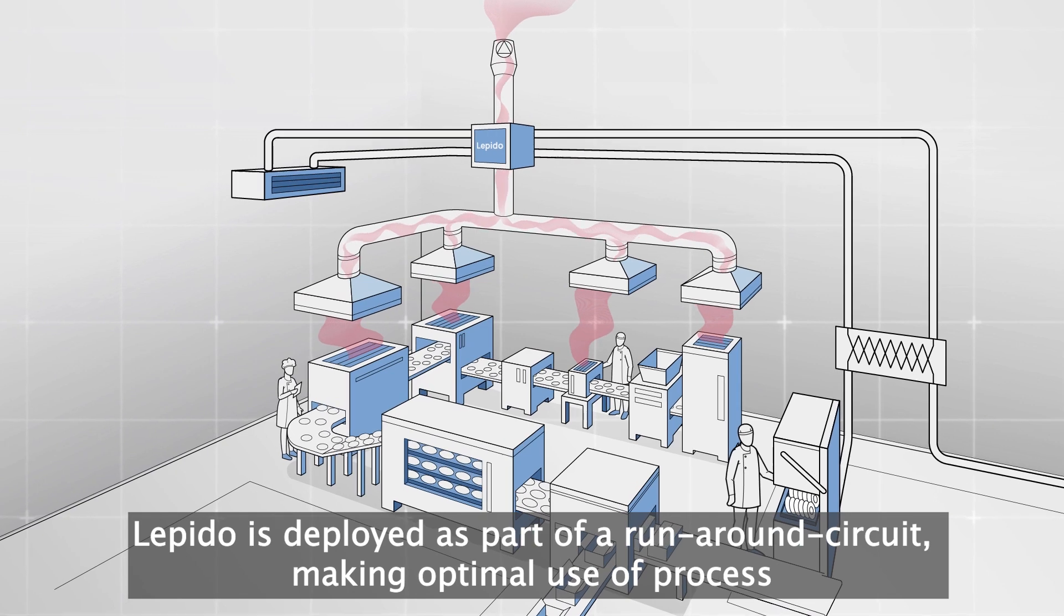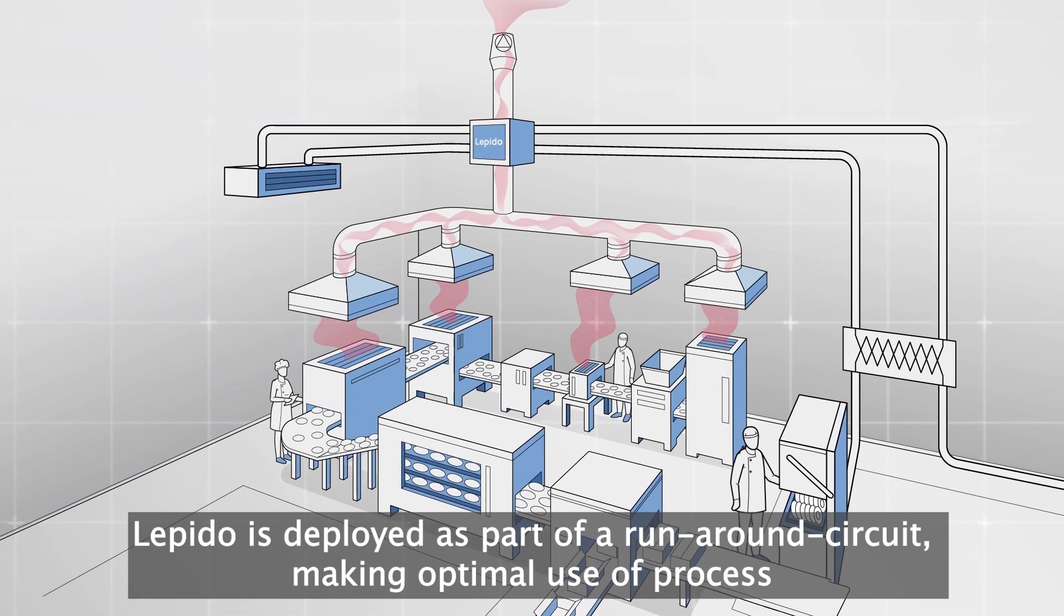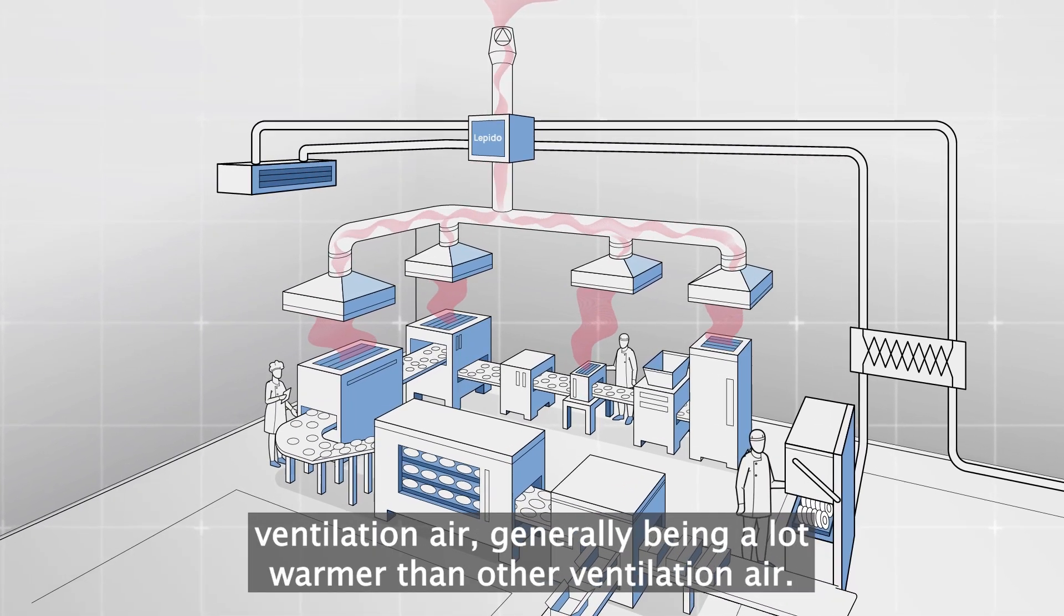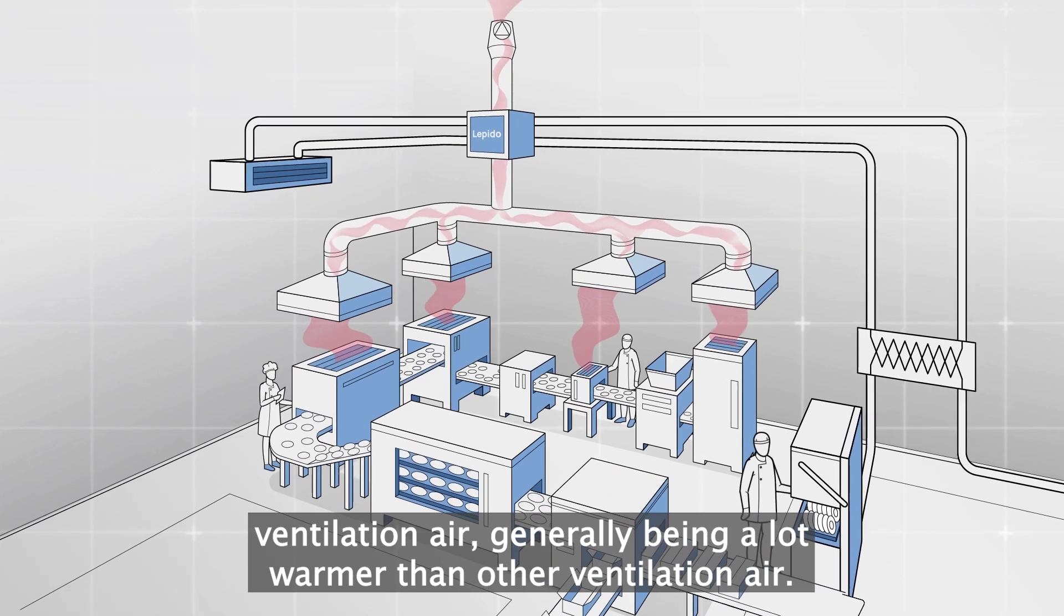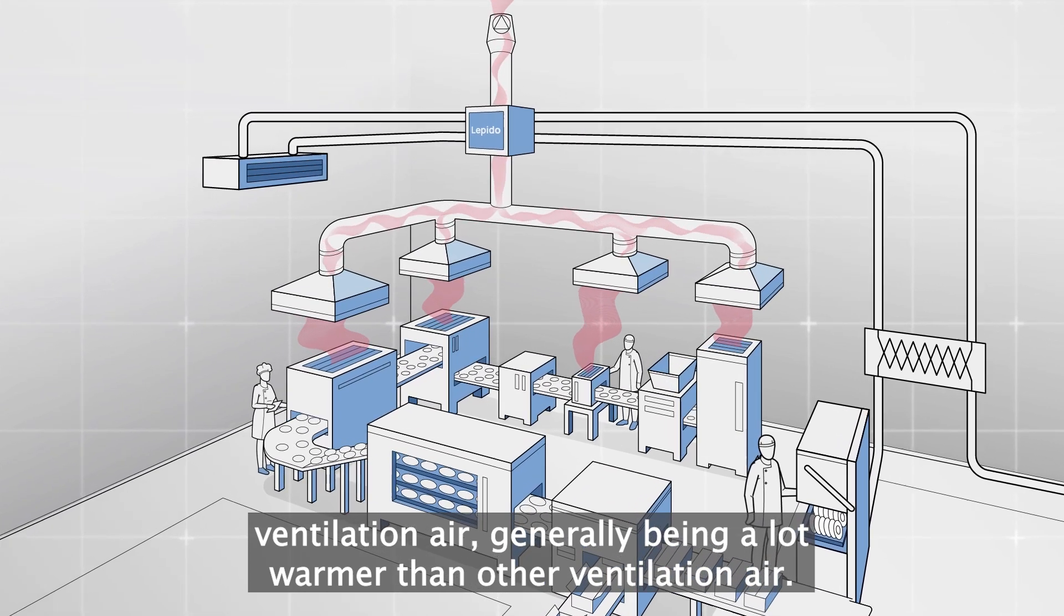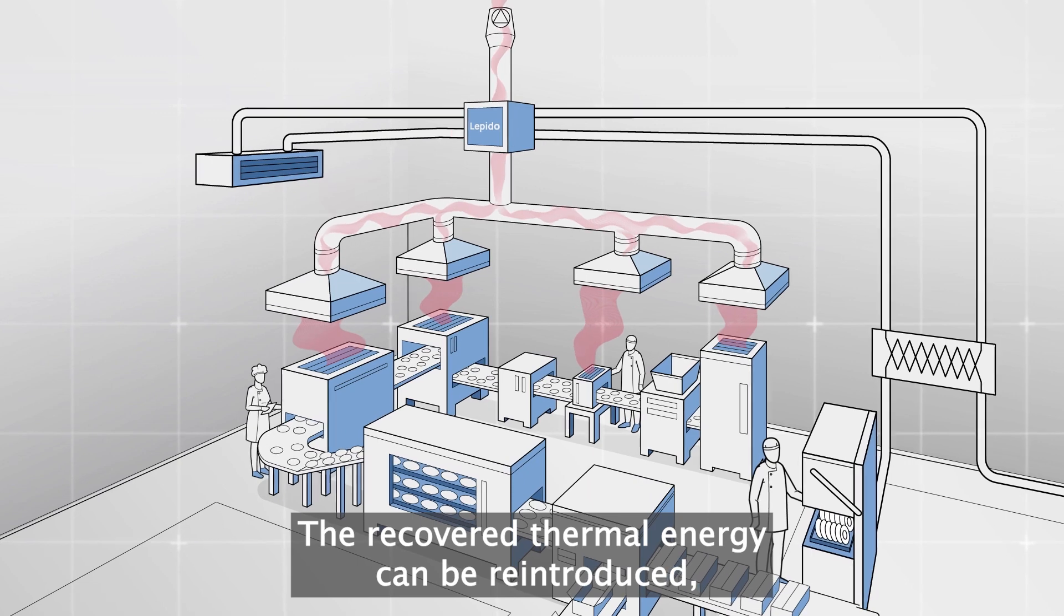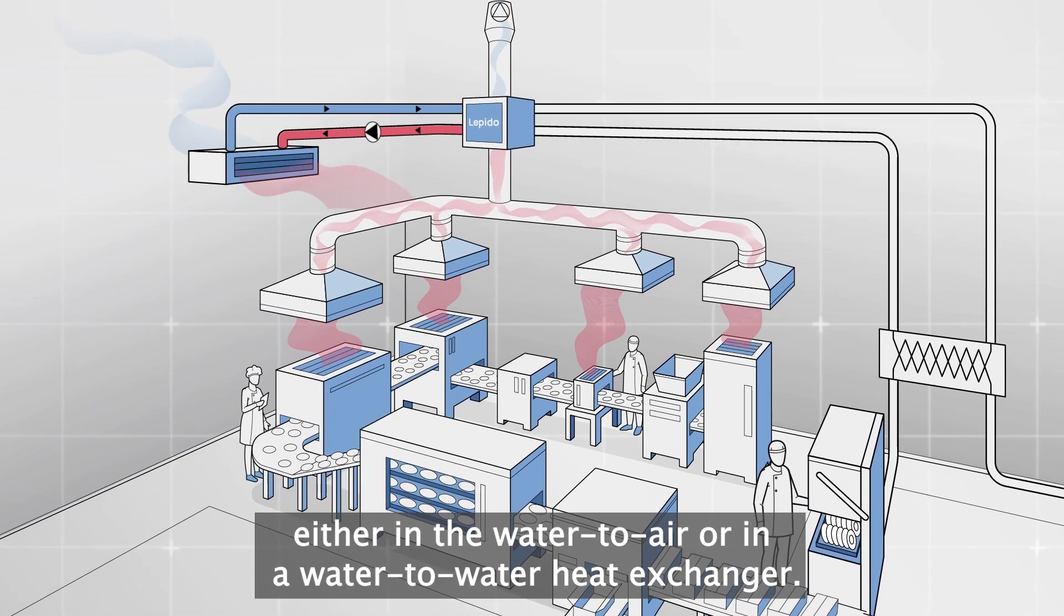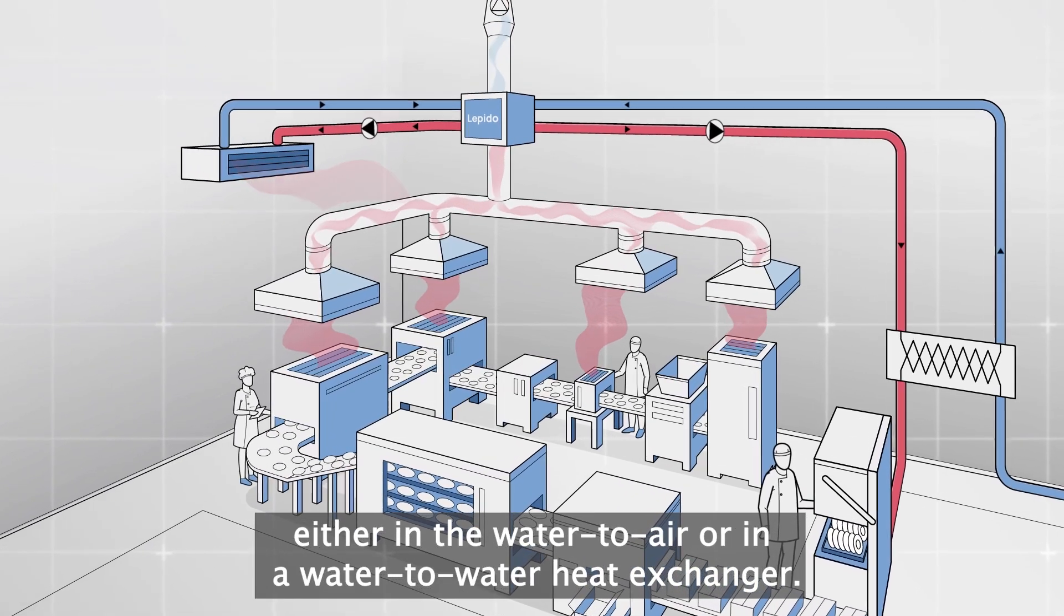Lepido is deployed as part of a run-around circuit, making optimal use of process ventilation air, generally being a lot warmer than other ventilation air. The recovered thermal energy can be reintroduced, either in a water-to-air or in a water-to-water heat exchanger.